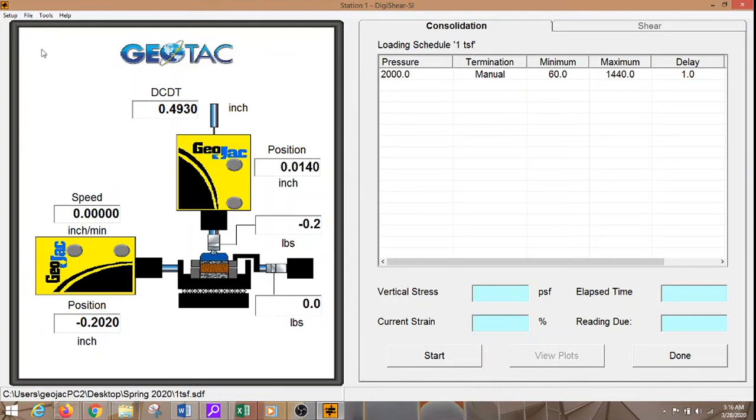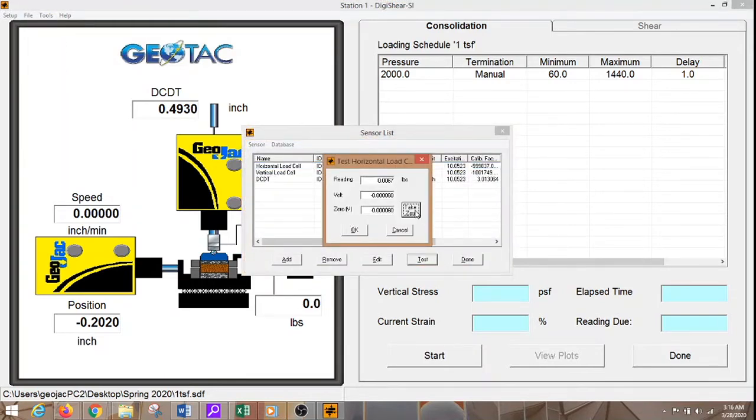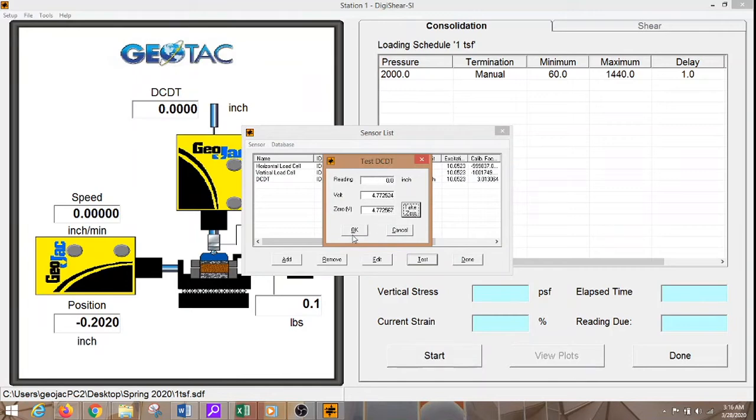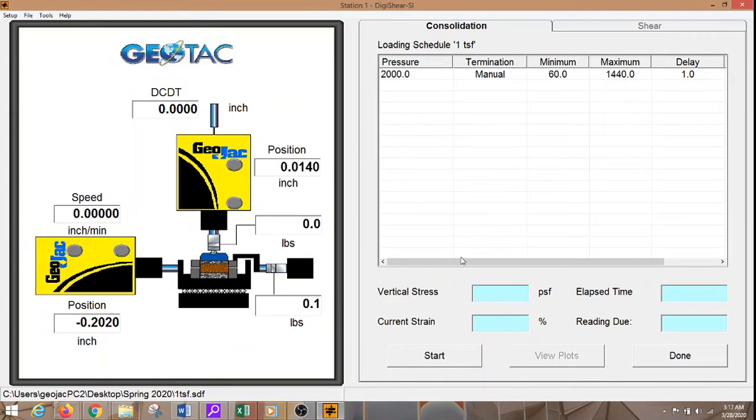Then I go to the sensors and set all to zero. Take a zero reading. OK. Vertical load cell. Take a zero reading. OK. DCDT. Take a zero reading. OK. Now we are ready to start the consolidation. After a while when the consolidation is done then we will move over to the shear. Now start consolidation.